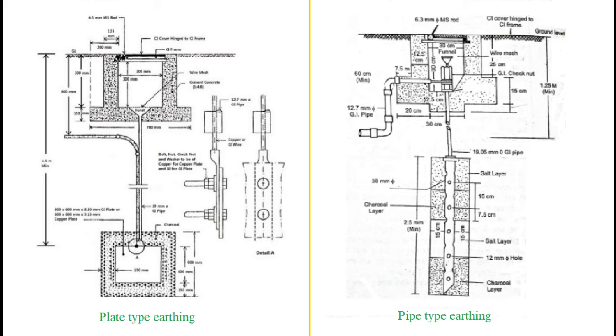When the process of putting in layers completes, water is poured through the pipe so that all layers shrink and go down. This process is repeated till the pit gets filled up to the level of brickwork. As per convenience, the water pouring point and earth point may be kept together or may be separated. This construction ensures contact of the earth electrode with the earth by the largest possible surface, and frequent watering will keep the space in wet condition. This erection of the earth point results in minimum earth resistance.